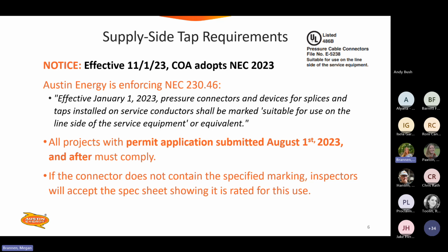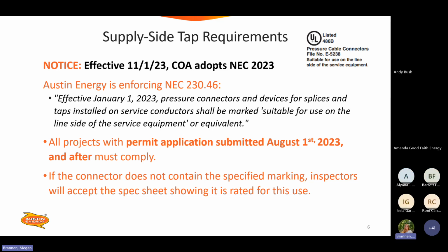Okay, so supply side tap requirements. As of 11/1/2023, City of Austin adopted the NEC 2023 code and are now enforcing 230.46. So just read this out to you all so we were all on the same page here. Effective January 1st of 2023, pressure connectors and devices for splices and taps installed on service conductors shall be marked suitable for use on the line side of the service equipment or equivalent. So make sure it's got that marking as well, so you guys can pass that and are not noting that in your final inspections. All right, any project with a permit application submitted after August 1st of 2023 must comply.